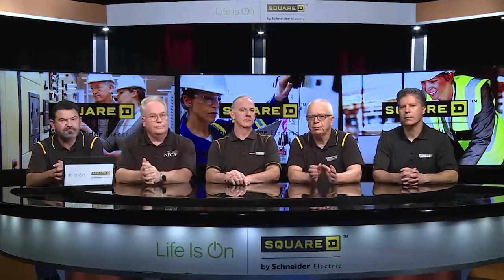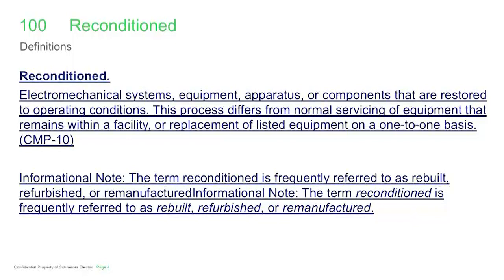Sure, Phil. There are a number of changes throughout the National Electrical Code in 2020 that will specifically address reconditioned equipment. In some cases, we're going to tell you that this piece of equipment cannot be reconditioned, and in some cases we'll tell you that it can be. Many types of equipment aren't addressed at all, but there are some marking requirements we'll get into later. In order to fully understand requirements for reconditioned equipment, we must first understand what reconditioned is. There's a new definition of the term reconditioned, located in Article 100.